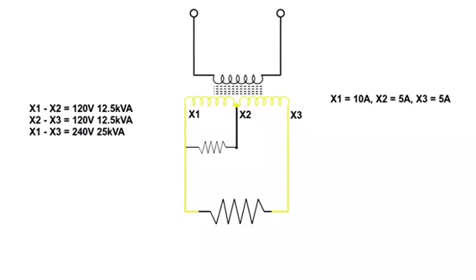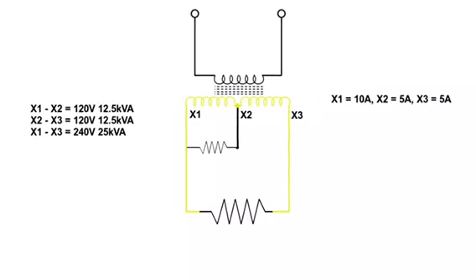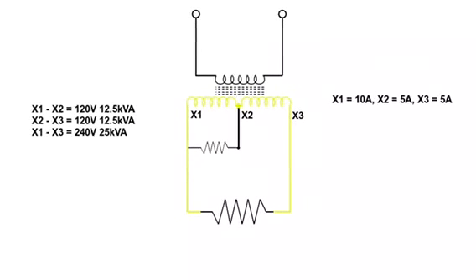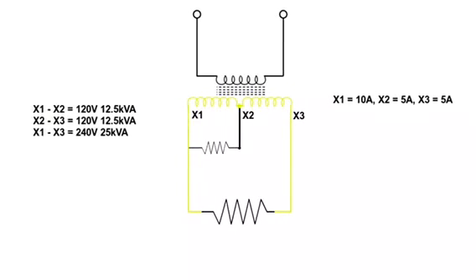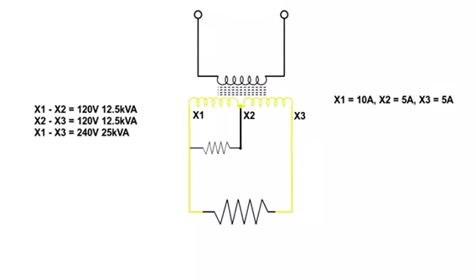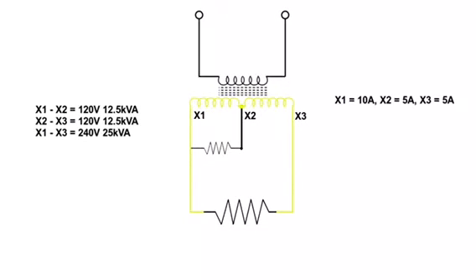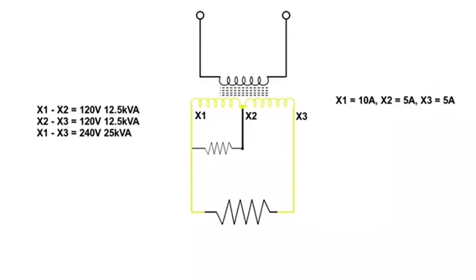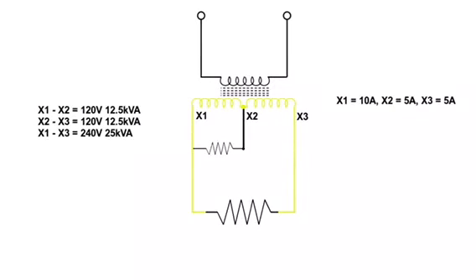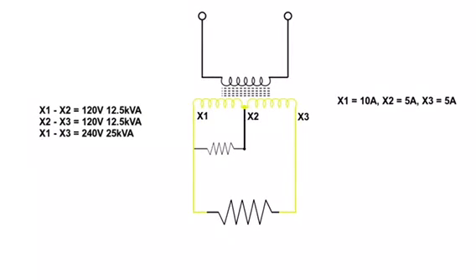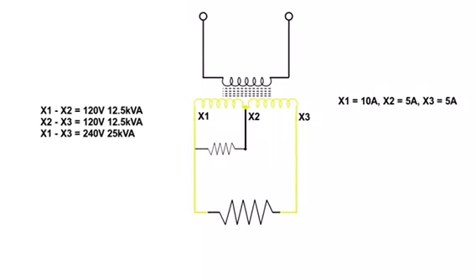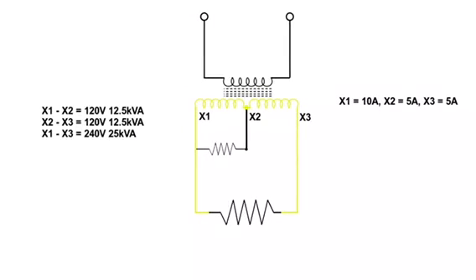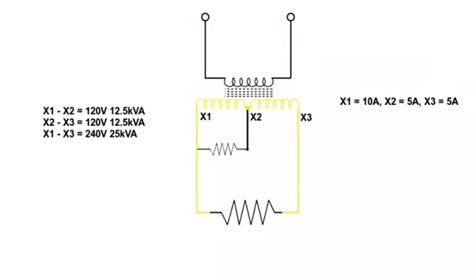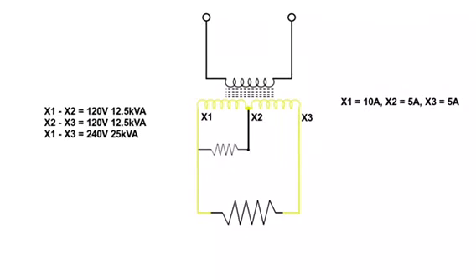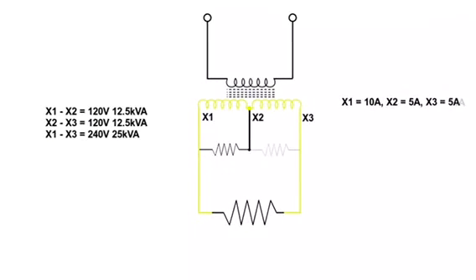So if we take a multimeter, or an amp probe, and connect it to X1, we will see 10 amps of current on X1. If we move our amp probe over to X2, we will see 5 amps of current on X2. And if we move our amp probe over to X3, we will see 5 amps. That is because the load is being divided equally across those coils in that order.